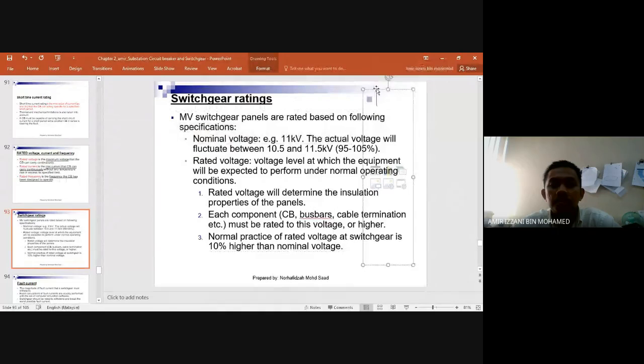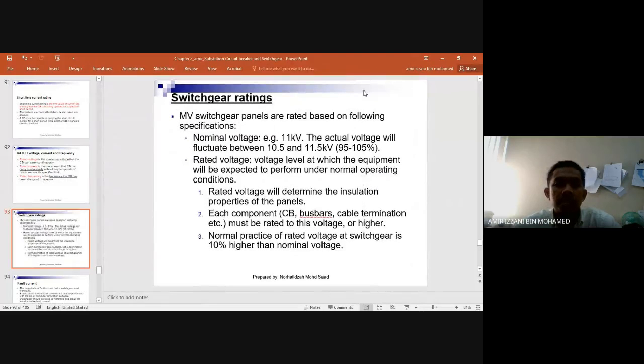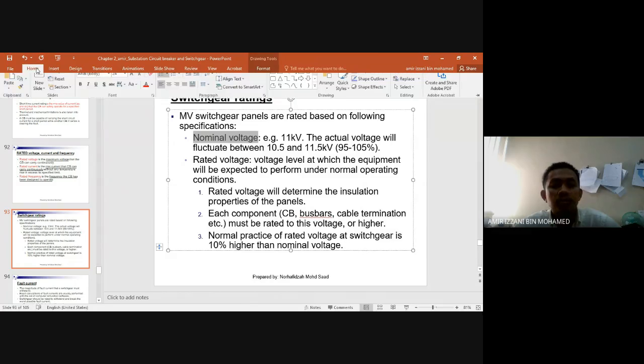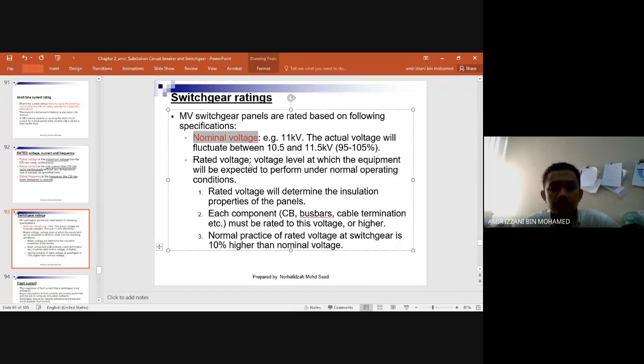Okay, for switchgear panel rating, MV switchgear panels are rated based on the following specifications. Nominal voltage, for example, 11 kilovolt. So it's difficult to maintain the 11 kilovolt due to the various number of loads. So the actual voltage will fluctuate between 10.5 to 11.5 kV, means that 5% of the nominal voltage.